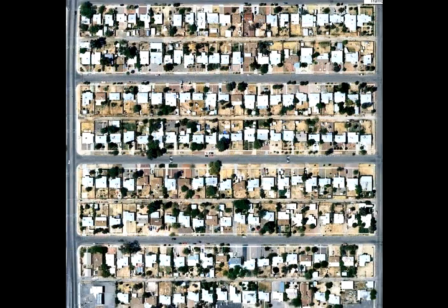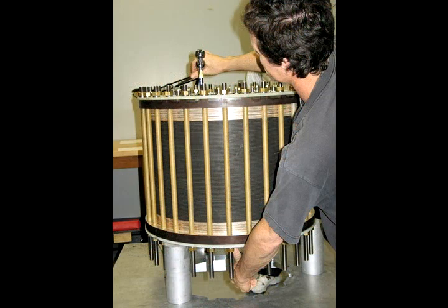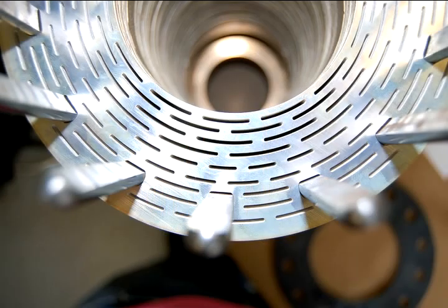So that's quite a lot of power that we're supplying to our magnets. All the energy I put into the magnet turns into heat, and if I don't remove that heat from the magnet, well, I'm going to have a big molten copper slag at the bottom of the magnet housing. Now, as you notice when looking in the resistive magnet shop, you'll see that those magnets have all these little holes in them. Well, that's where the water flows through the magnet, and we're pumping about 2,000 gallons a minute through each magnet.